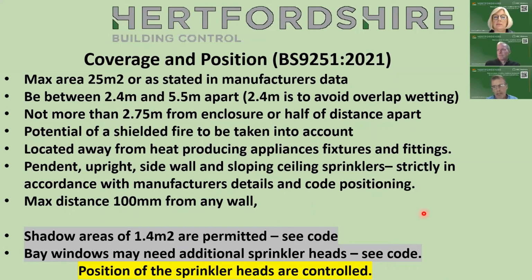Whereas as we spoke about earlier, the idea of the sprinkler is it wets the area around the fire. So if there's 1.4 meters squared that's dry and everything else around it is wet, then the fire will go into decay. And that's the idea there.